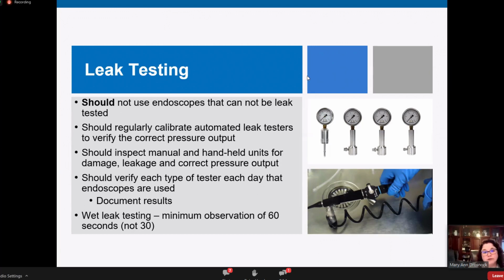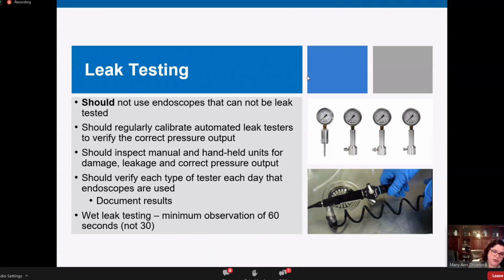What else is new is related to the leak test units themselves. There are many different kinds on the market. The most common ones are still the little box that sits on your counter and it pressurizes the endoscope and you submerge it under the level of the water only, never detergent at this step. And I still see that done, unfortunately, too commonly. So that's most commonly what's used.